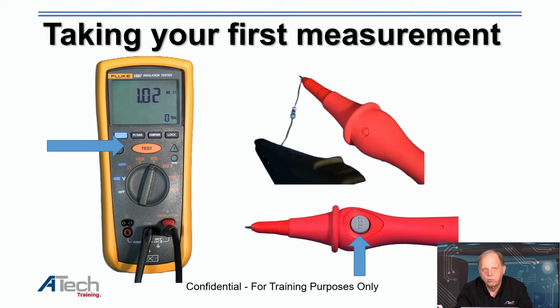Taking your first measurement, we're showing here that we go across with a test button, and the test button on the tool and the test button on the lead do the same function. This allows one-hand testing, which makes it a lot easier instead of reaching back for the meter itself. If I'm doing this, I'm probably going to hit the one on the lead, it makes it a lot easier.